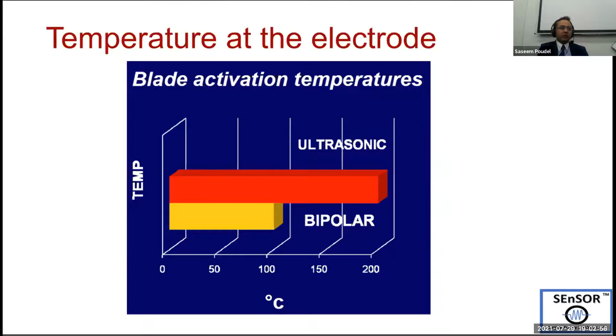There was a study done in 2011 which compared the residual heat of different instruments and the time it takes to cool off. You can see in the graph here that even 20 seconds after activation, the ultrasonic devices were still more than 20 degrees Celsius above their baseline. So it was still hot. It's highest with the ultrasonic devices, and it is lowest in the advanced bipolar. So it can cause significant tissue injury.